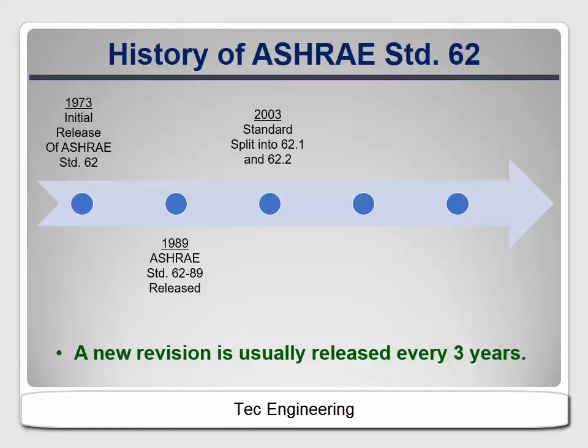Then they returned to the three-year release cycle. In 2007, they released a version that shifted away from the philosophy of 0.35 air changes or 15 CFM per person to a calculation method that combines the number of occupants and the floor area into a single equation to determine the required ventilation rate.